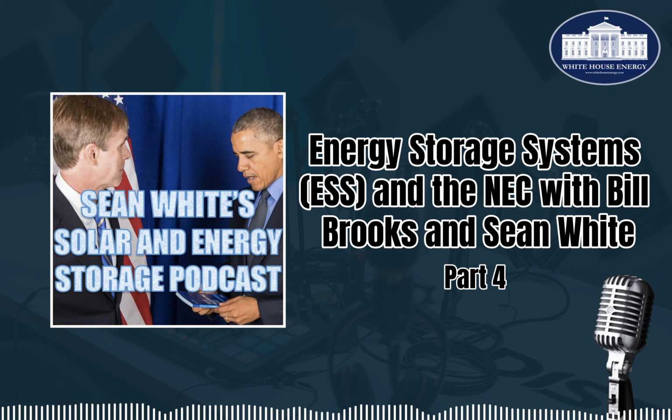One way of thinking of this is like, how often is somebody going to be blasting out all the power from their battery and all the power from their PV system at the same time? Probably never, because you're going to be charging your battery with your PV system instead of discharging your battery. Why not control all that stuff, and then you don't have to size everything based on the currents coming out of both at once, when you're never going to be putting them both out at the same time, because you can control it with electronics.